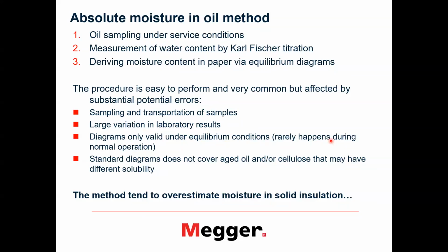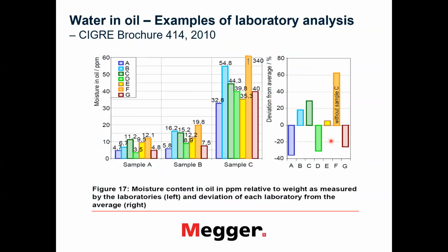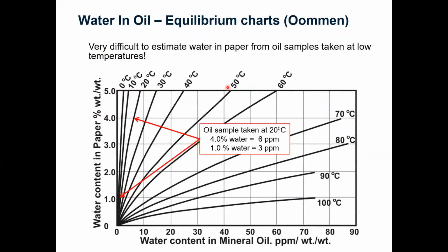So there are different ways to measure, but this method, water in oil, tends to pretty much overestimate moisture in solid insulation. And here are examples, again, with large variations in the moisture in oil in ppm. It could be 3.5, 12, or it could be like 32 or even 340. I don't know, it's measuring error or something, but we have quite a huge variation in these results as well, which, when we then use the table for estimating the paper moisture, depending on whether we have 20 ppm or 90, gives very different results.